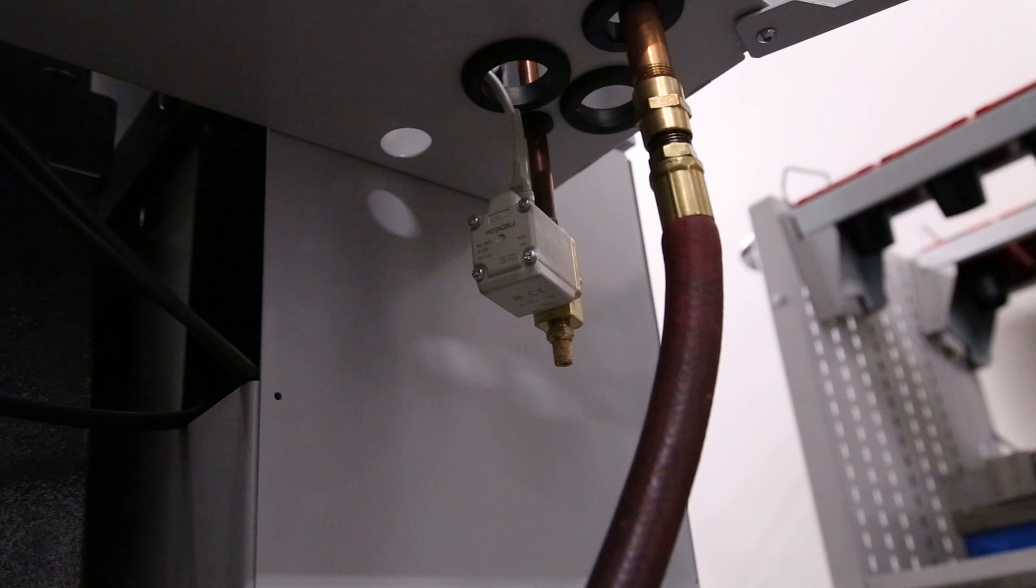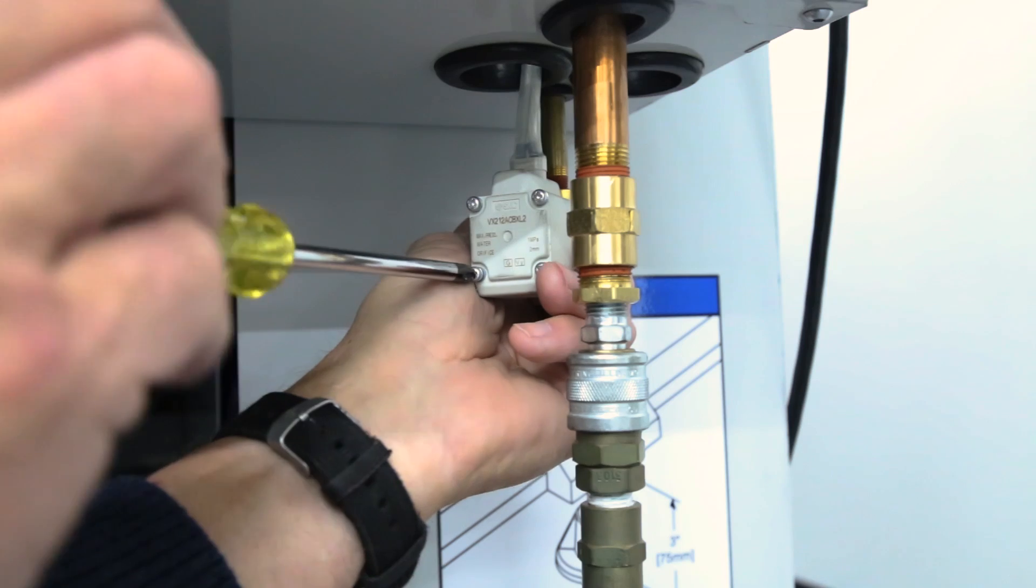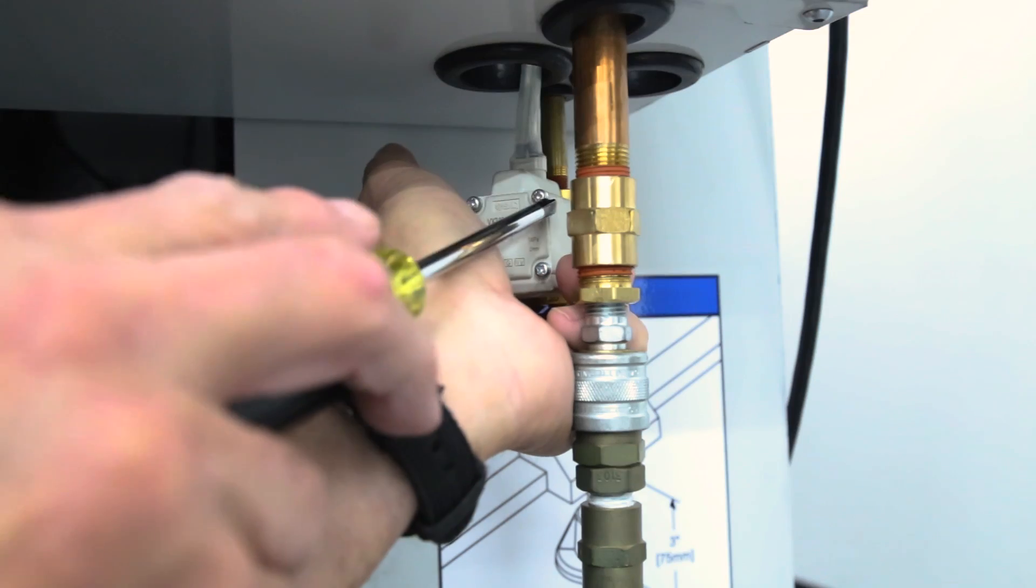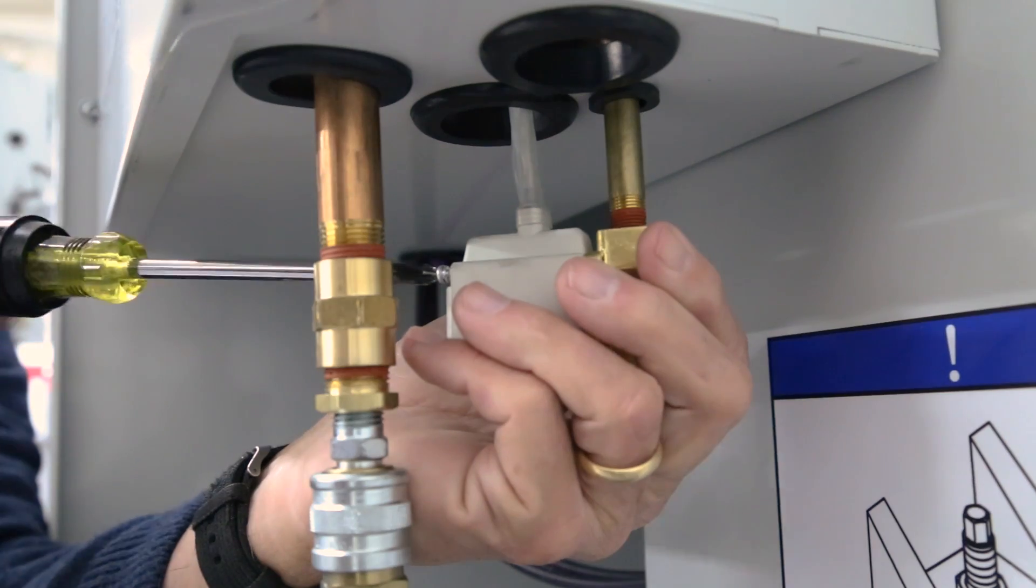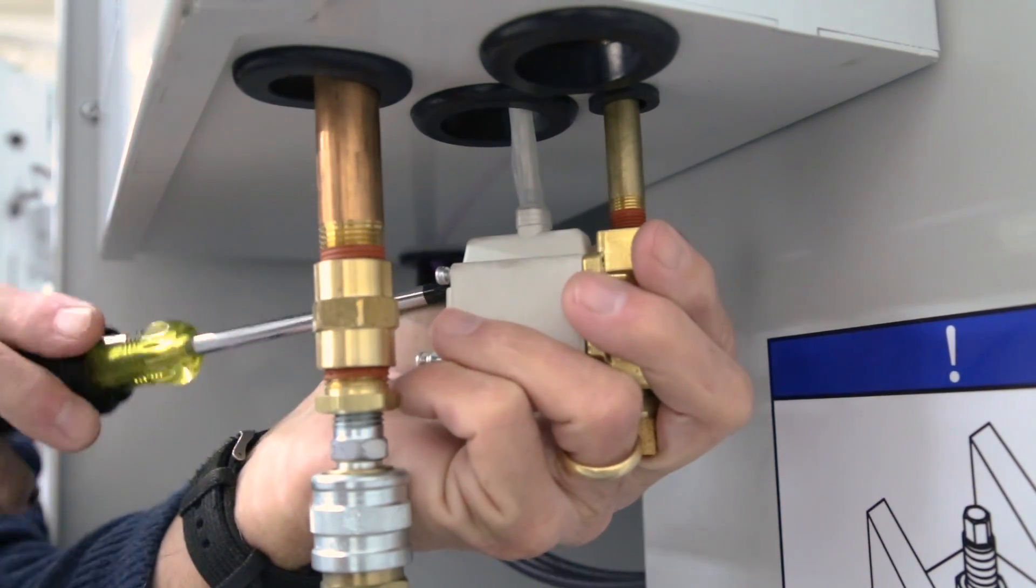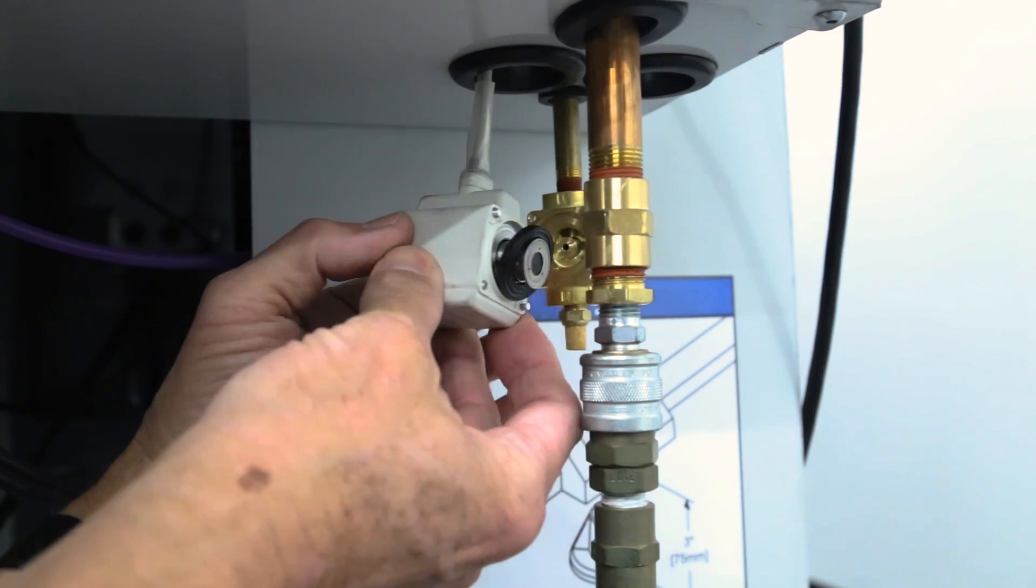You can do this job on the machine without removing the solenoid. Remove the four screws of the coil assembly. As the solenoid is slightly spring-loaded, keep your hand over the brass manifold as you back out the screws. Gently pull the coil assembly away from the manifold.